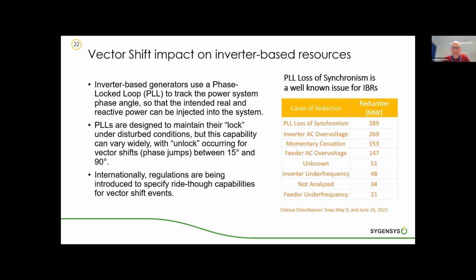This table here comes from an analysis in the US of an incident in Texas last year, where over 1,000 megawatts of embedded generation tripped. And the largest single cause, about 35% of that, was phase-locked loops unlocking, actually losing synchronism with the main grid. So this is an established issue.